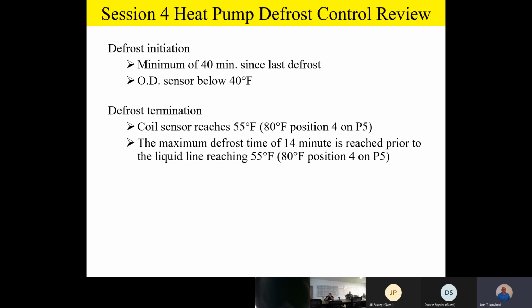In addition, the outdoor sensor is going to have to be below 40 degrees Fahrenheit. This is a really important concept, especially from a service standpoint. Before this defrost control even thinks about defrost, it has to be 40 minutes since the last defrost, and the outdoor air temperature has to be below 40 degrees. So if it's 50 degrees outside, it doesn't even think about defrost until it hits below 40.